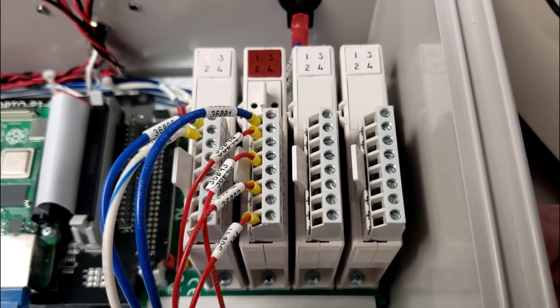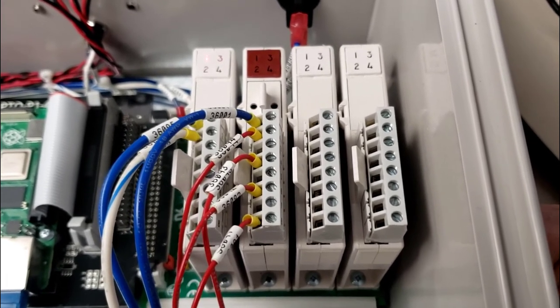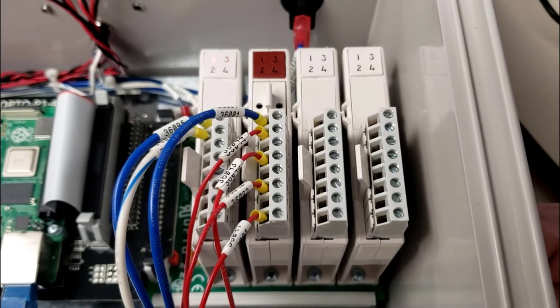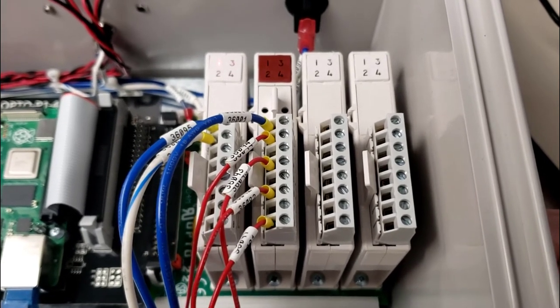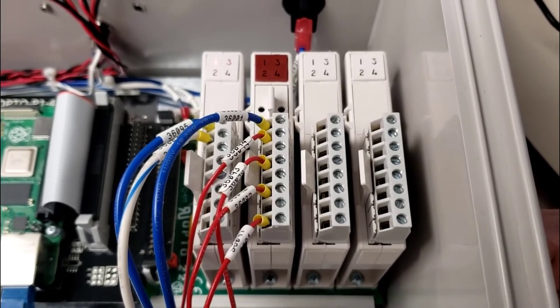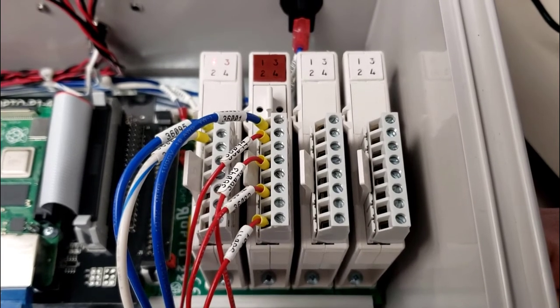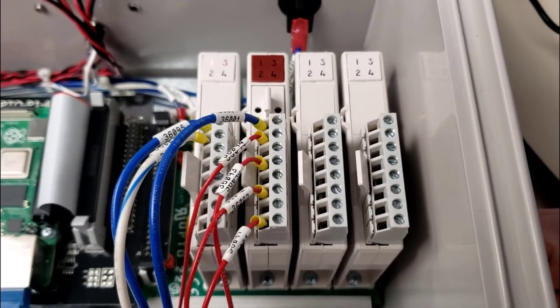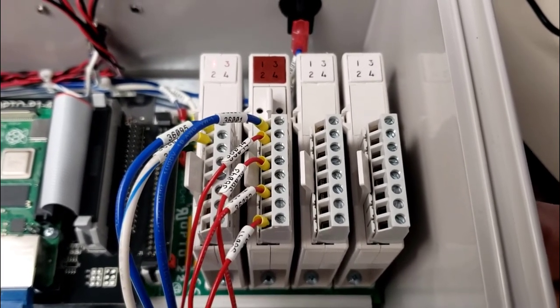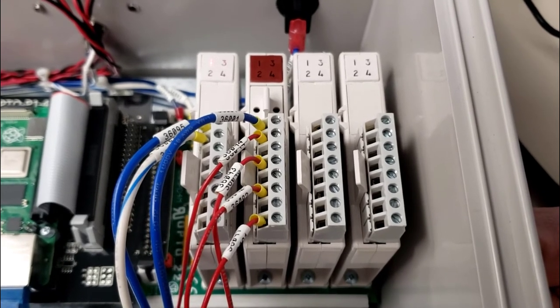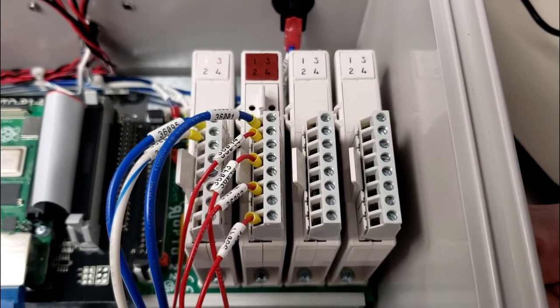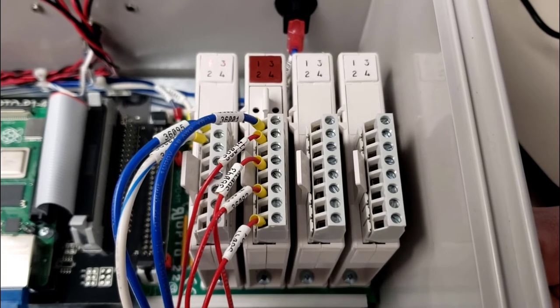So you have the ability to bring in 8 different signals, and so that would give you a maximum of 4 machines if you are only interested in a machine on and a machine running or cycling status. If you are interested to have additional inputs such as faulted or watchdog error, that would limit the number of machines that you can bring in.